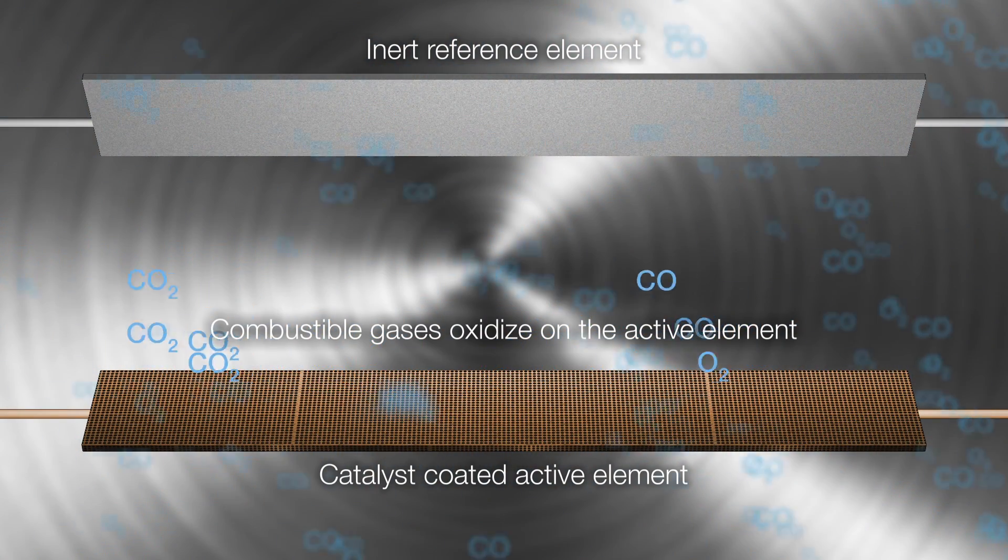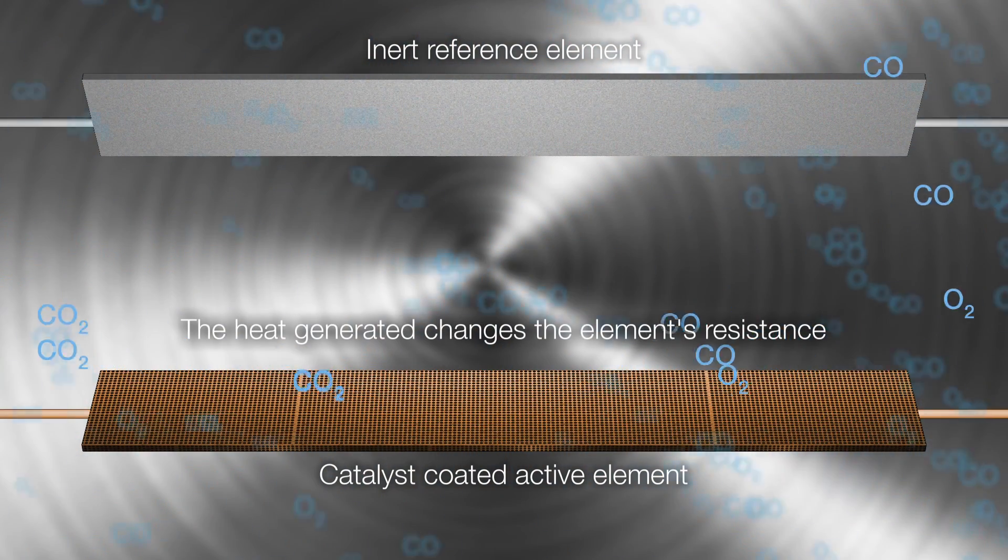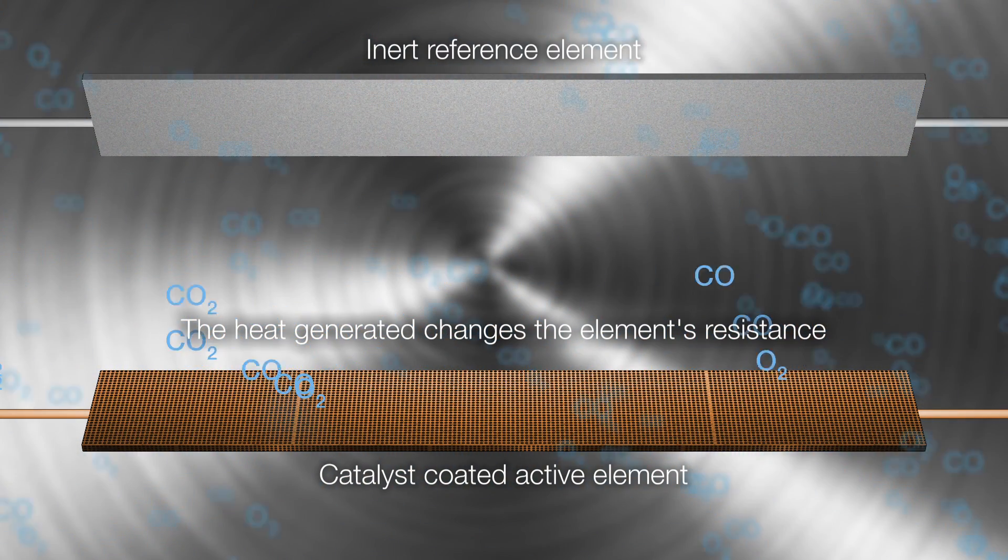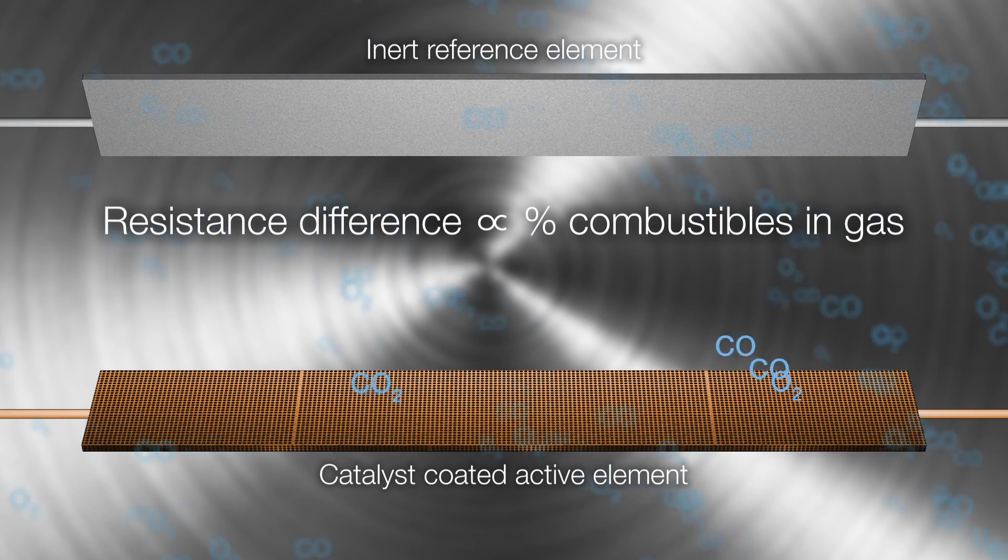The heat generated by the oxidation causes a temperature difference between the active and the reference elements. This temperature difference produces a resistance relationship between the two elements, that is directly proportional to the concentration of combustibles in the sample gases.